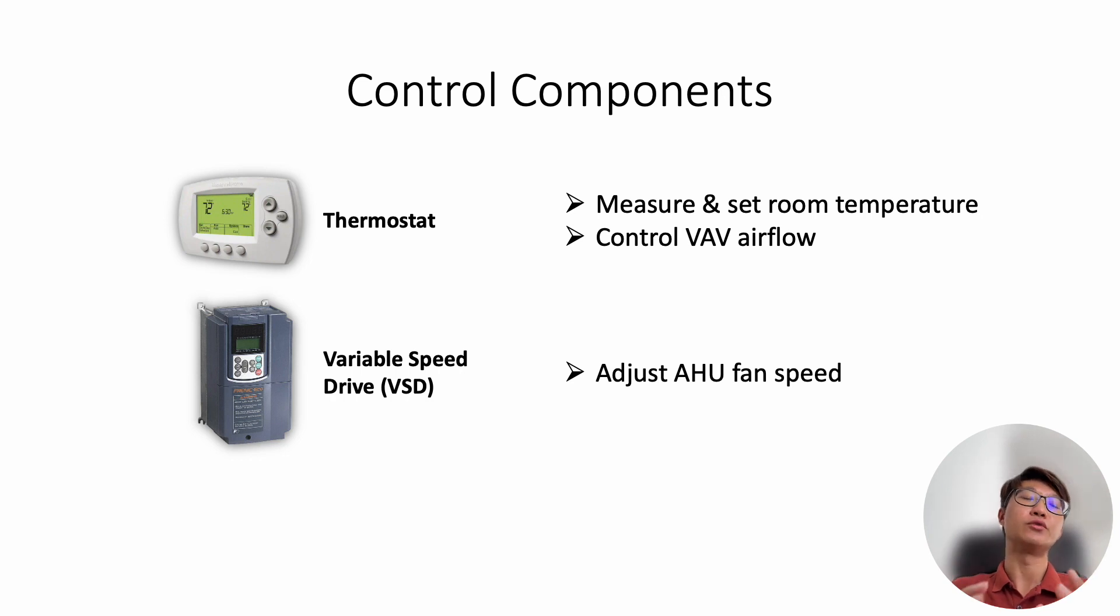Then the second component we need is the variable speed drive. This is to control the main supply airflow. When you don't need so much airflow, you start to close the VAV box. You also want to reduce the supply airflow so you can save some energy. So this is usually mounted at the air handling unit, the AHU.